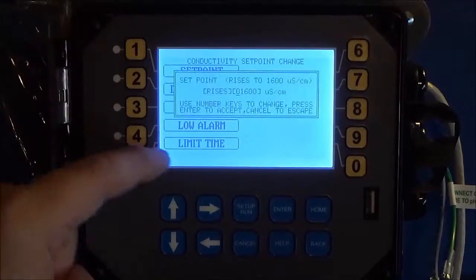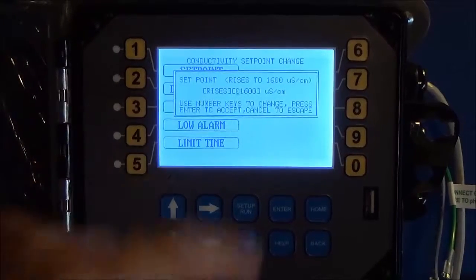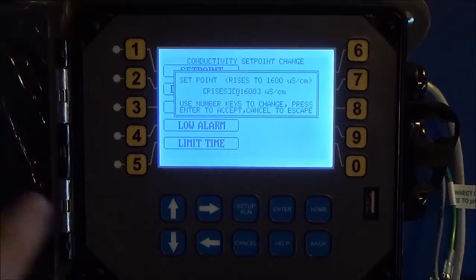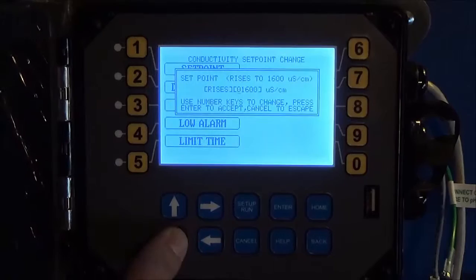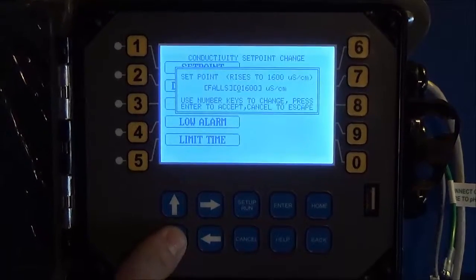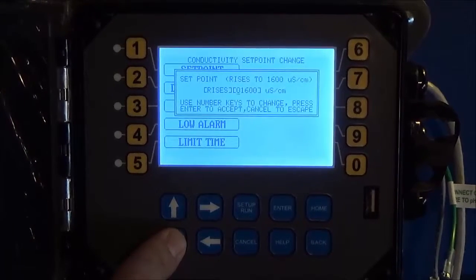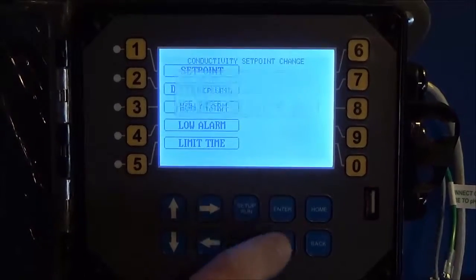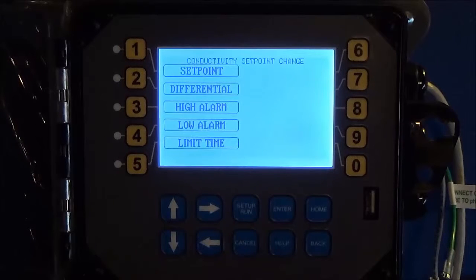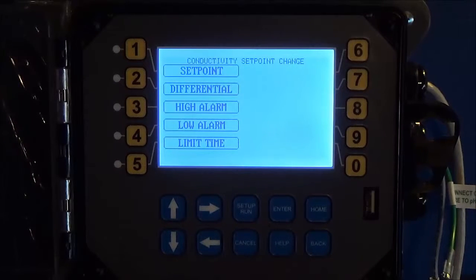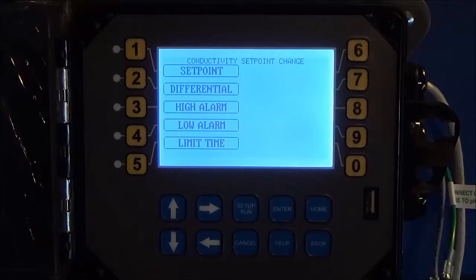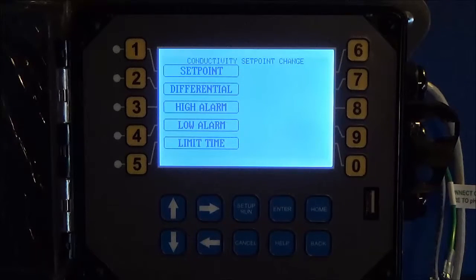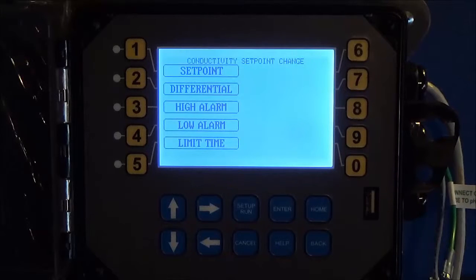Now as part of that setpoint you notice the rising falling, you can change that by hitting the up and down keys. One quick way to remember whether you want to be rising or falling is whether the reading itself is going to be rising to a point where you take action, or if the reading will fall to a point until you take action.